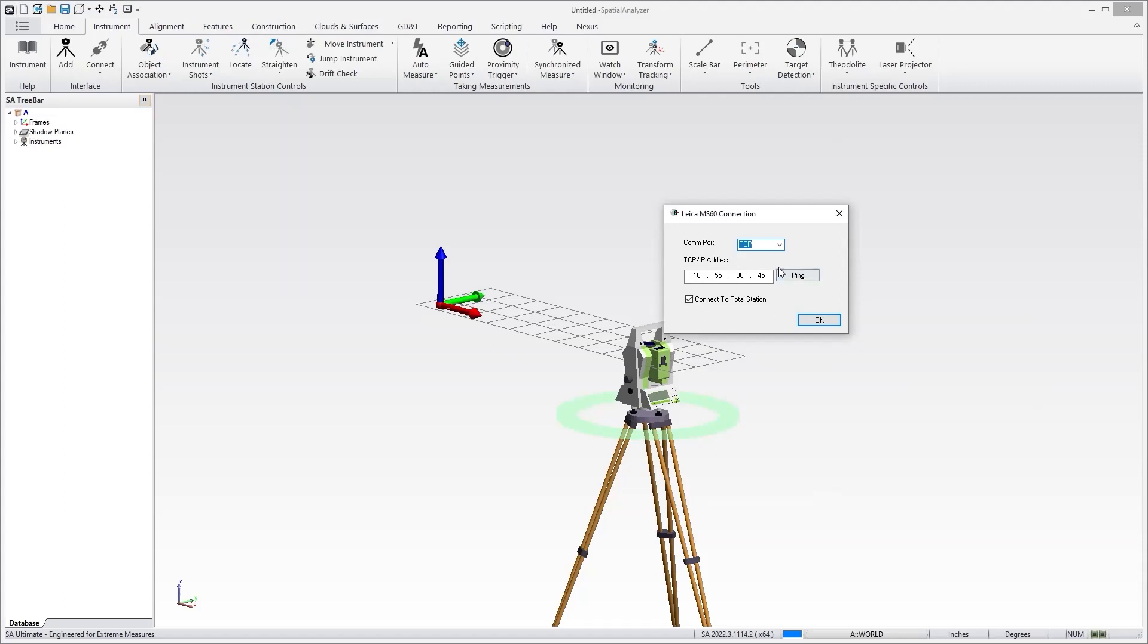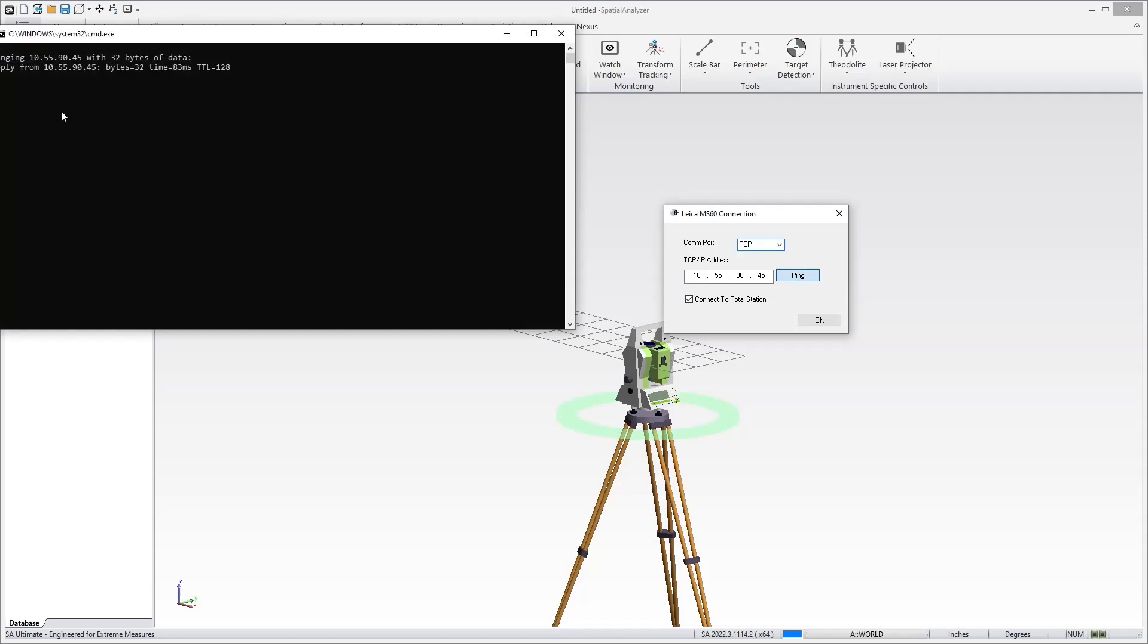Here is our connection dialog for connecting to the MS60. As you can see, it's set up for a TCP IP connection using an IP address, which is the one that is listed on the connections in the Total Station interface. You would enter that in here, and you can put ping to make sure that it's talking to you.